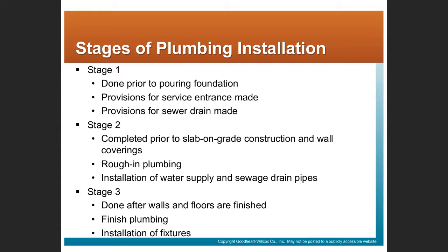Stage 2, and we'll see some pictures in just a minute, completed prior to pouring the slabs and putting up the wall covering. So stage 2 is often called a rough-in or rough-in plumbing. And in this case, we're going to start connecting up the supply and the drainage pipes. And then stage 3 would be after the walls and floors are put in, the plumber is going to come back and essentially hang the fixtures on the rough-ins that he or she has put up previously.